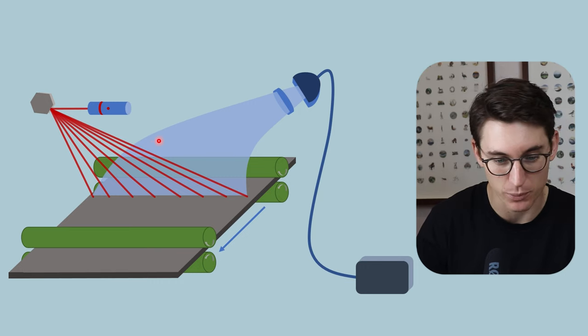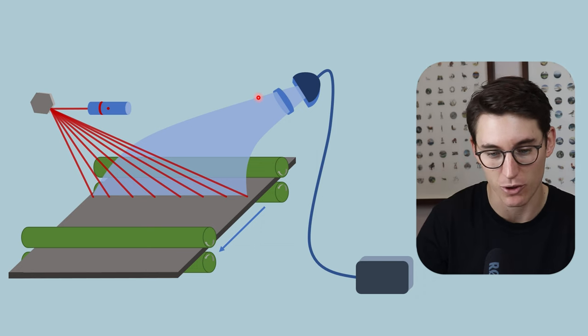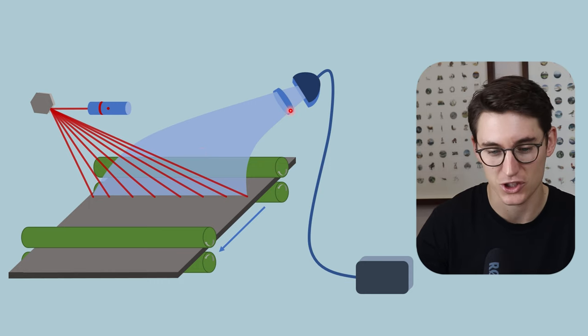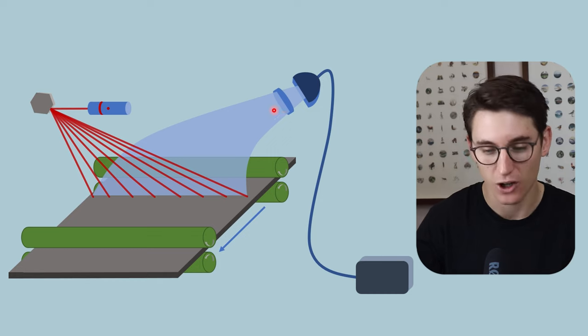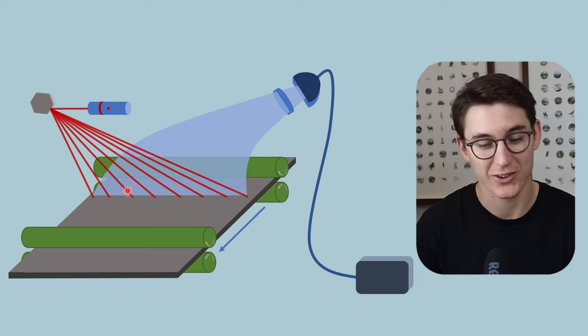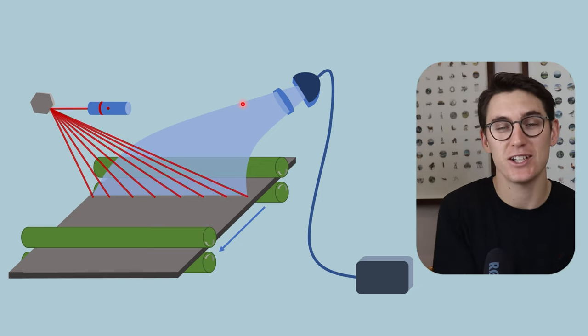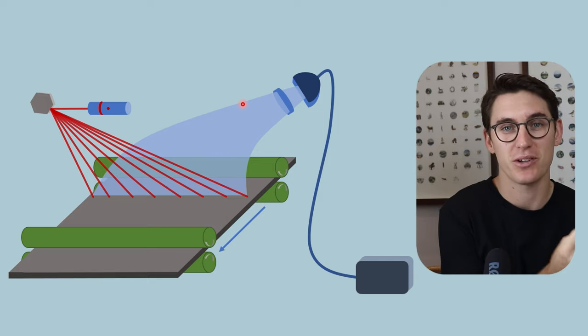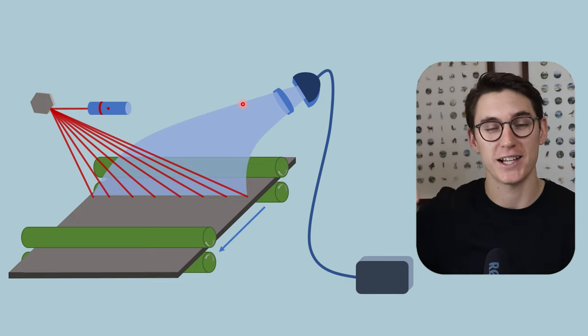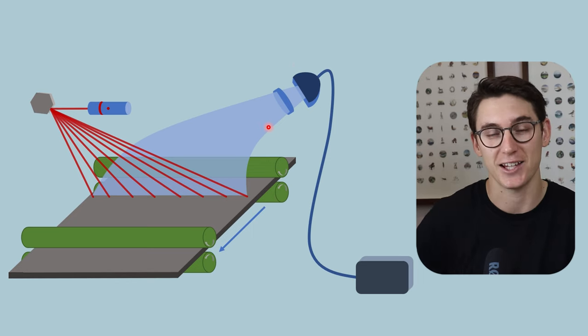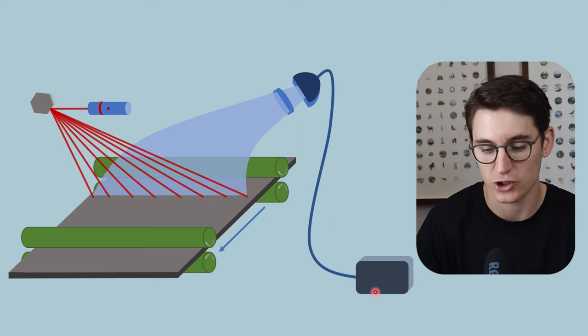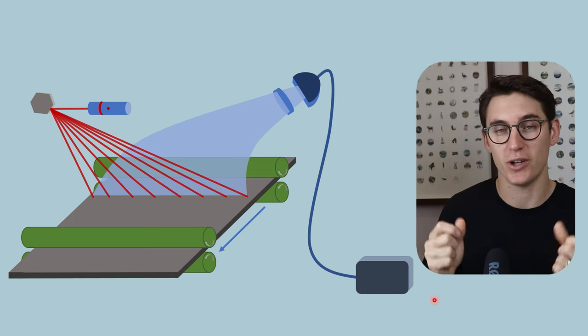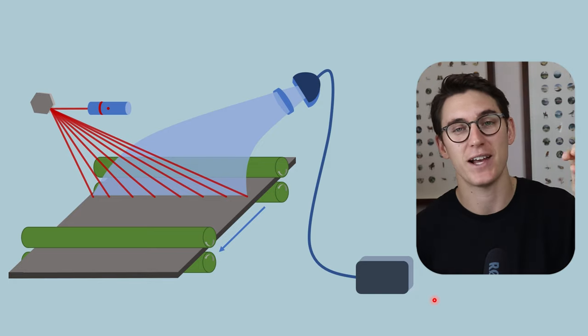The red laser light causes blue light to be released, and that blue light is channeled along fiber optic channels toward a photo multiplier tube. Some red light also travels along these channels, but a filter removes it — only blue light reaches the photo multiplier tube. The intensity of that blue light is proportional to the intensity of the x-rays that originally hit the cassette: more x-rays means more filled F-centers and more intense blue light released. The photo multiplier tube multiplies that blue light signal and sends it to an analog-to-digital converter, converting it into pixel values — ones and zeros — that we can assign to each pixel on the computer screen.